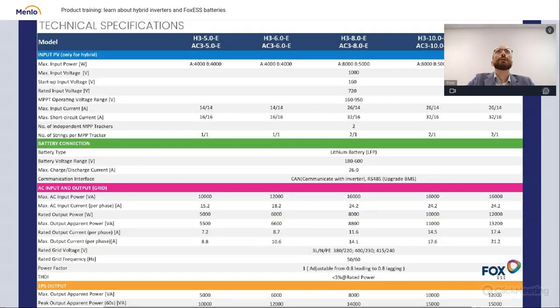Of course, what is also important, and I don't see it on this chart, but as I said earlier, those units are capable of switching from the grid to EPS mode in under 20 milliseconds. It's far too short to disconnect your electronic appliances. You will only see a blink of your lighting, your LEDs will just blink for a moment, and everything will be powered from the battery.